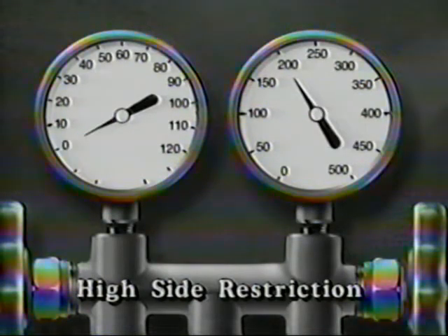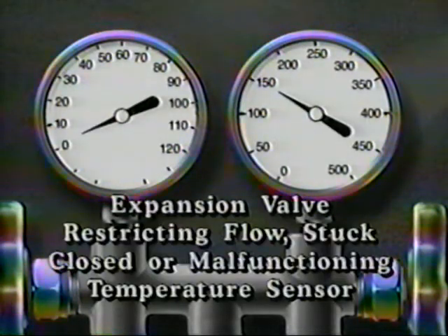In which case the discharge pressure will be extremely high. Damaged parts must be identified and replaced, and the system must be purged or flushed. If the expansion valve is restricting the flow of refrigerant, is stuck closed, or contains a malfunctioning temperature sensor, the pressure on both the discharge and suction sides of the system will be low, although normal pressures can be restored when a hot, wet rag is applied to the expansion valve. In this case, the expansion valve must be replaced.